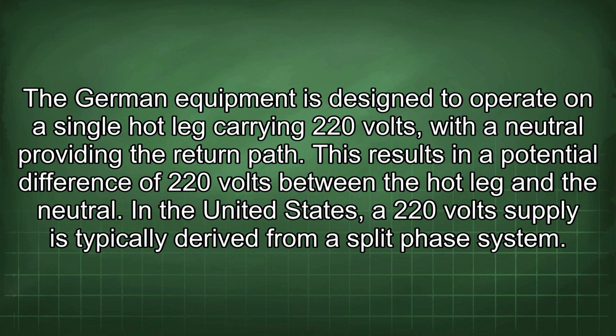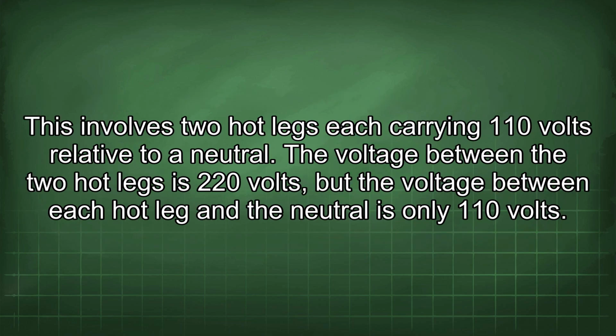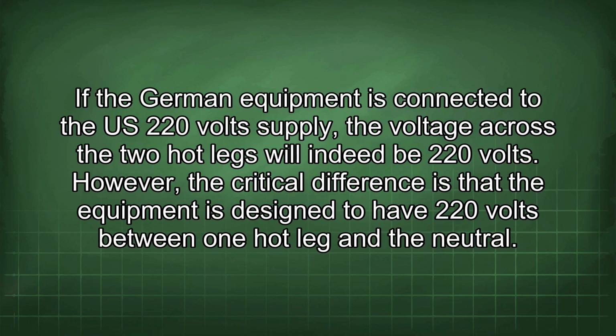In the United States, a 220 volt supply is typically derived from a split-phase system. This involves two hot legs each carrying 110 volts relative to a neutral. The voltage between the two hot legs is 220 volts, but the voltage between each hot leg and the neutral is only 110 volts. If the German equipment is connected to the US 220 volt supply, the voltage across the two hot legs will indeed be 220 volts.